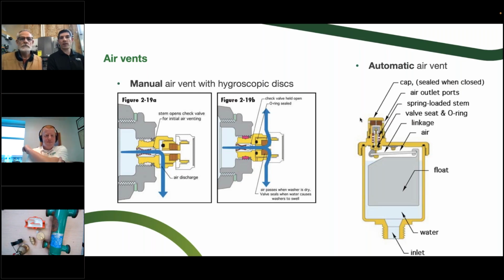So let's say that you've got an air vent above a conference room table or some expensive piece of equipment in a server room or something like that. And you just really don't have any option to have water come out of the top of that valve, even if somebody did put their finger on the cap and get a piece of Teflon tape in the top. So this cap, I'll walk over and show it on the screen here. This is shown in the cross section, or yeah, there you go.